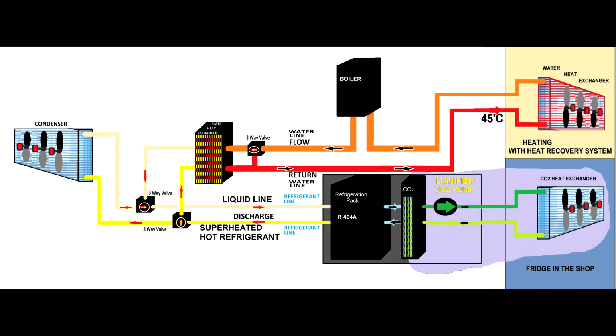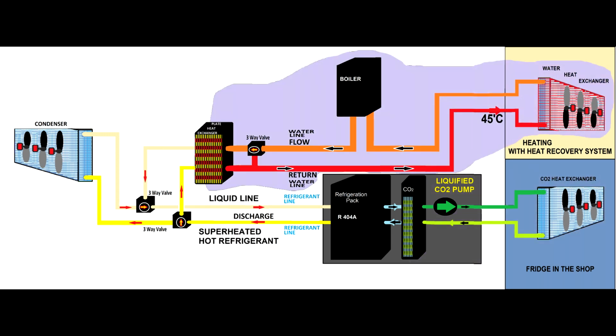Now this is the carbon dioxide section. A very cold carbon dioxide in liquid form is moved through that system, so it's losing energy on that plate heat exchanger, and it will gain energy on this heat exchanger inside the store. And finally you'll have the water circuit, and also you can see you have a boiler. It is very easy. The water will be heated by that plate heat exchanger. You will exchange heat with the refrigerant, but also the boiler will help when the temperature outside is very low. So this is the system.